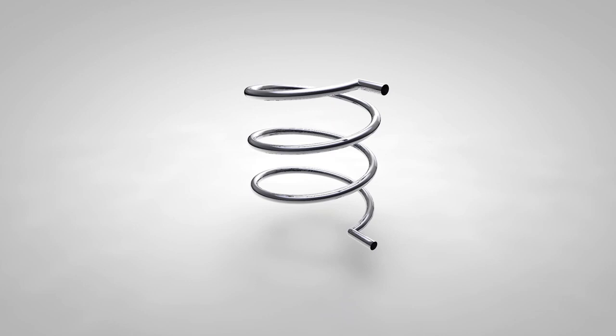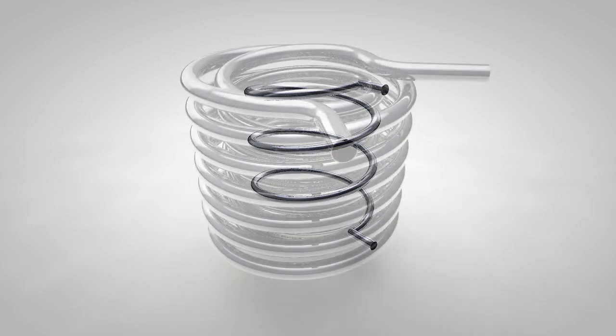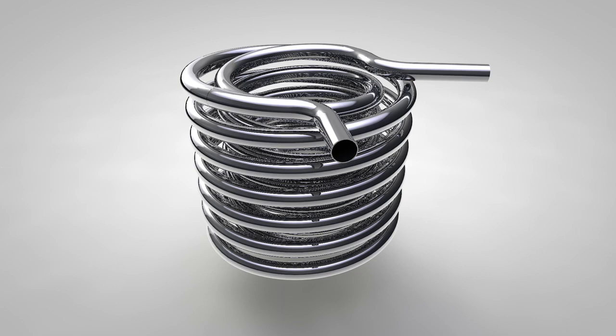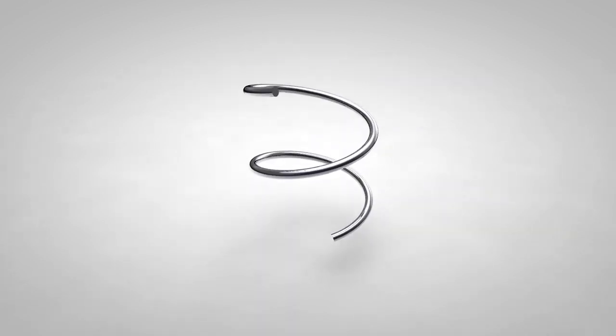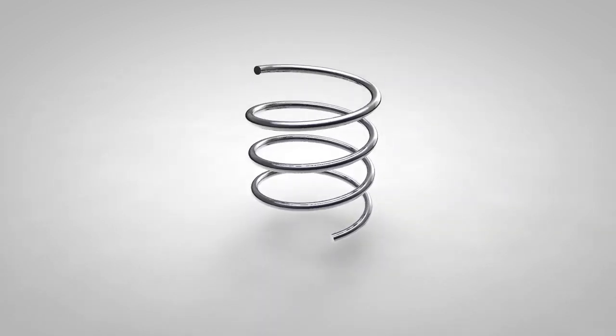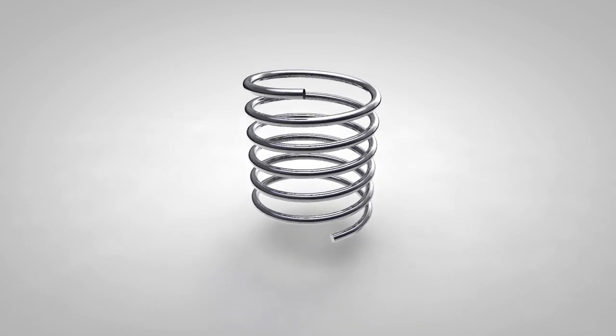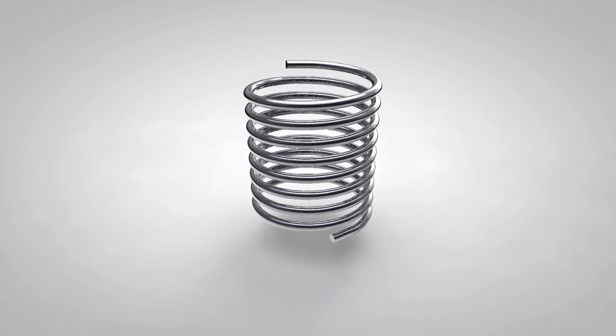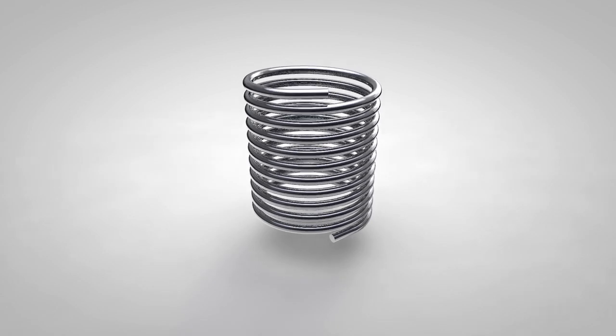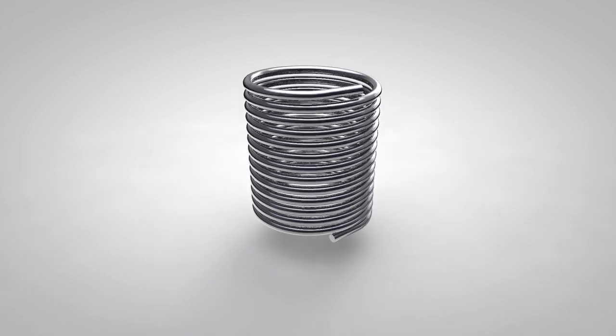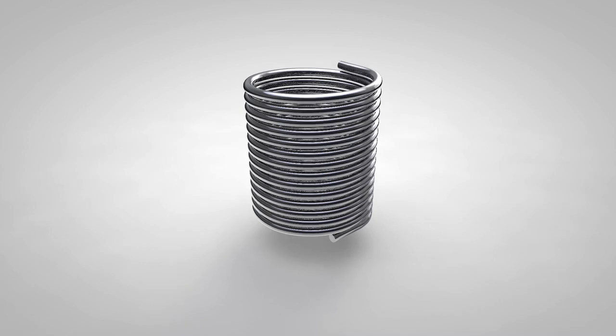Gravity feed systems also can't benefit from space-saving coil designs such as coil-in-coil. On a modern pumped system, an excessively long coil can be self-defeating if the pitch of the coil becomes too tight. It will interfere with the circulation of the water around the coil and can result in slower heat-up times.